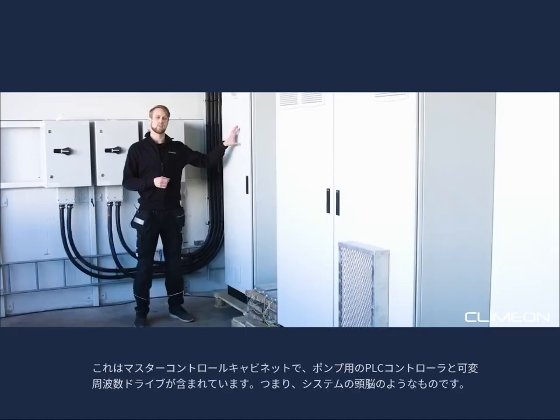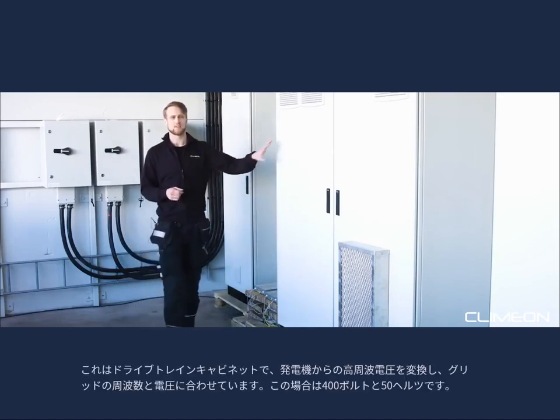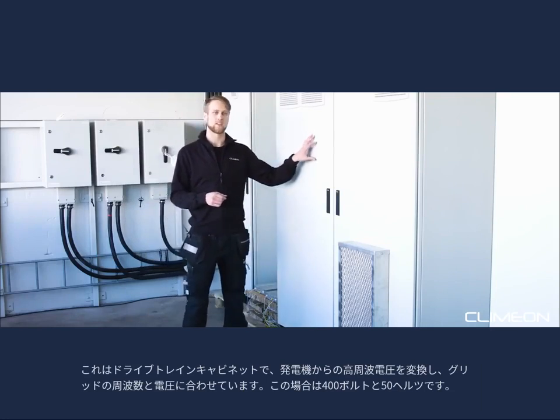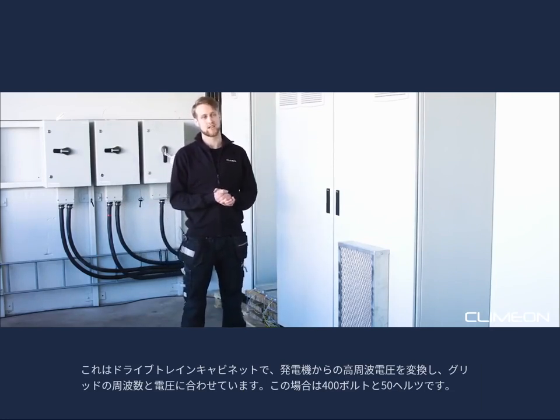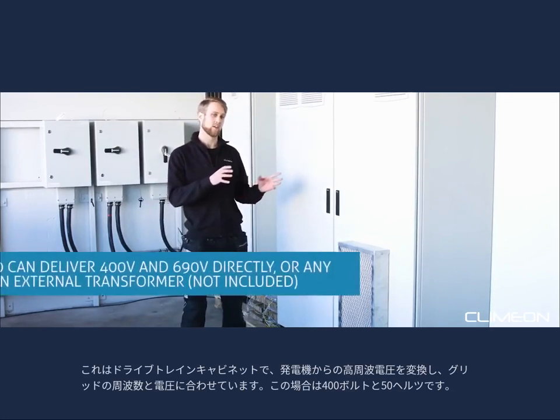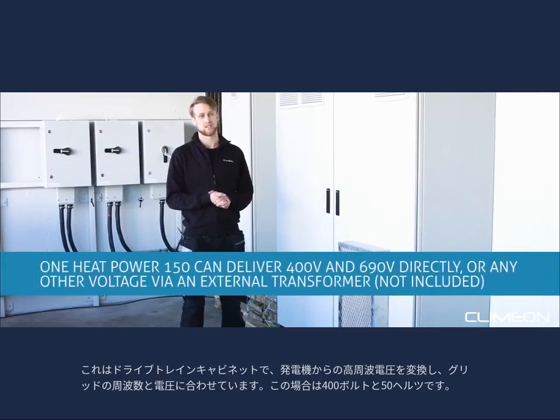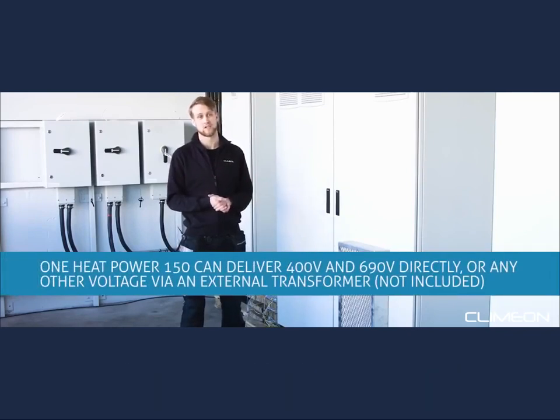This is the master control cabinet, which contains the PLC and variable frequency drives for the pumps. So this is kind of the brain of the system. This is the drivetrain cabinet, in which we convert the high frequency voltage from the generator and match it to the grid frequency and voltage. In this case, it's 400 volts and 50 hertz.